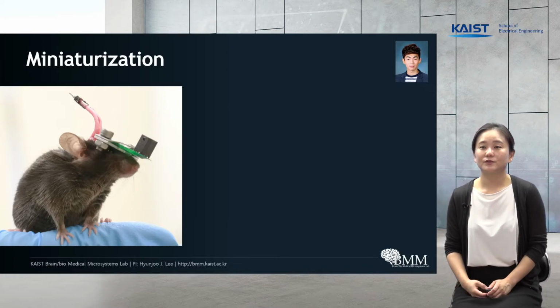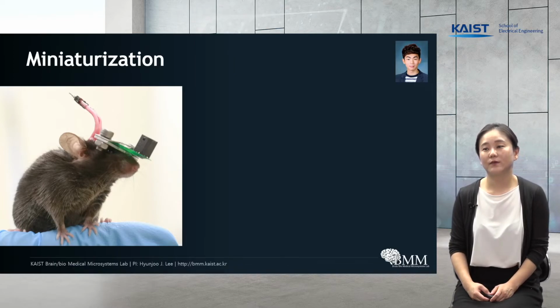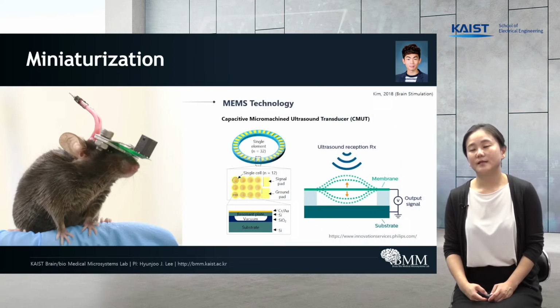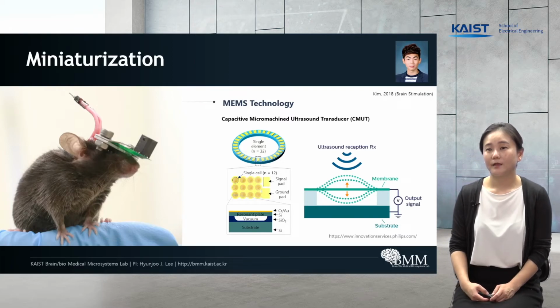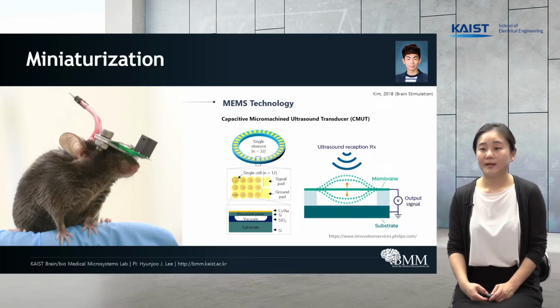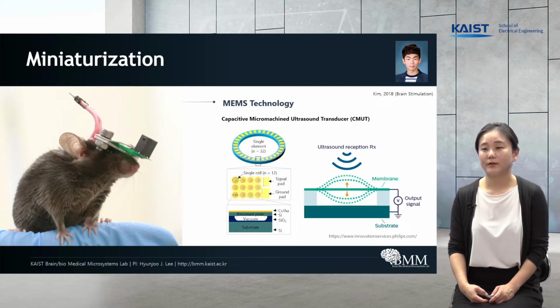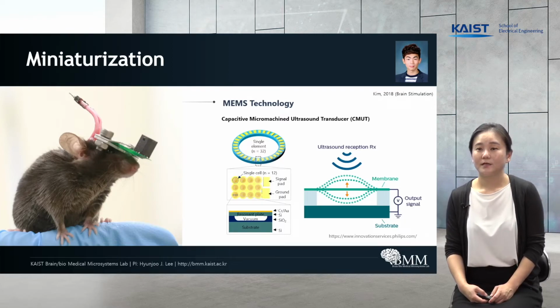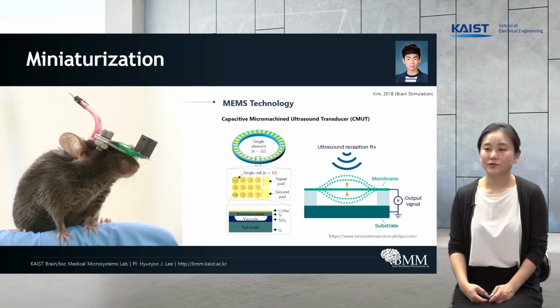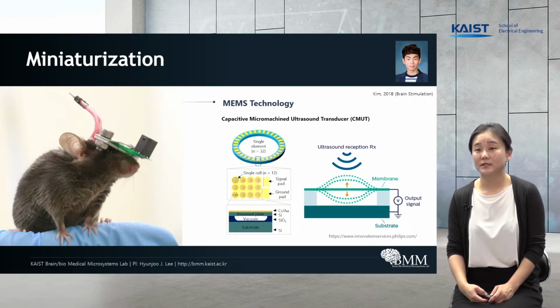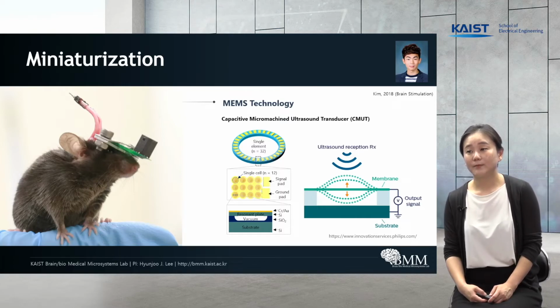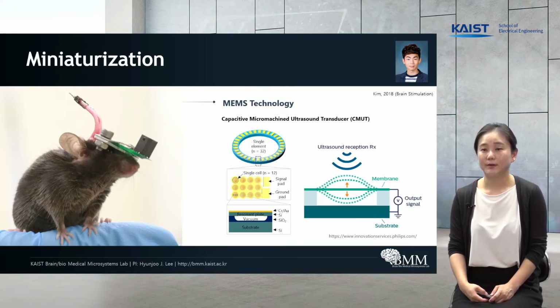We have put the ultrasound transducer, coupling gel, and wiring all in this very thin plate you see in the photo. The technology that allowed us to make such a compact and miniaturized system is called MEMS technology. Using MEMS technology, we fabricated the capacitive micromachined ultrasound transducer, also known as CMUT, which is composed of a very thin silicon plate operated through electrostatic actuation. So CMUT is composed of multiple transducers placed in an array, where if you zoom into a single transducer, there are multiple vibrating circular plates all connected in parallel.